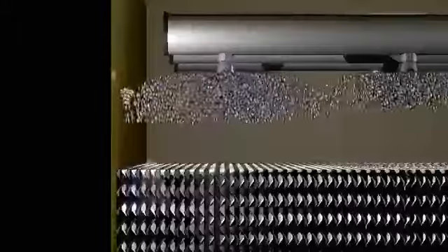The same circular water pattern of the spray nozzles hits the walls on the perimeter of the cooling tower, flooding the film media in these areas. So what's so bad about wall water? It had to be pumped to the top of the cooling tower.